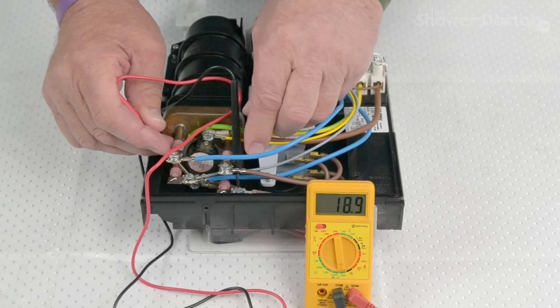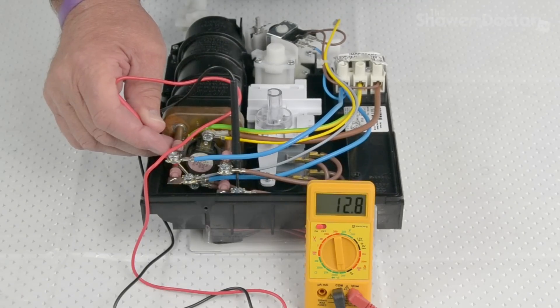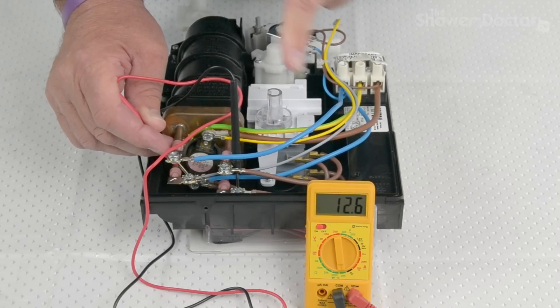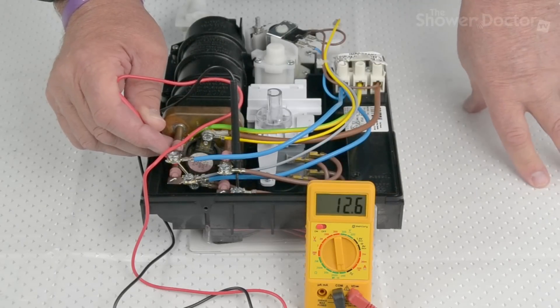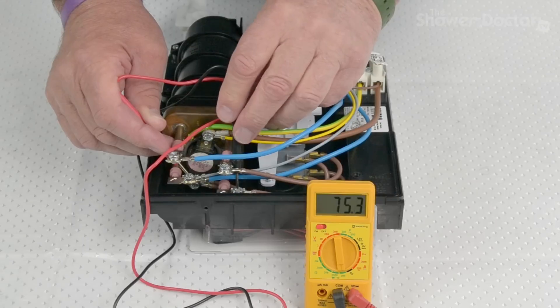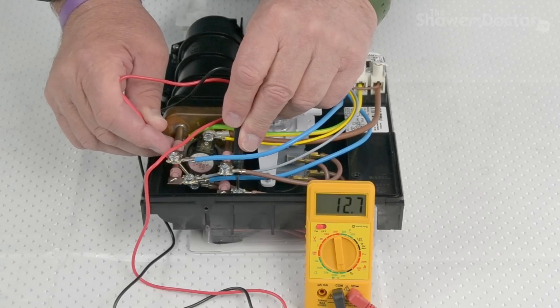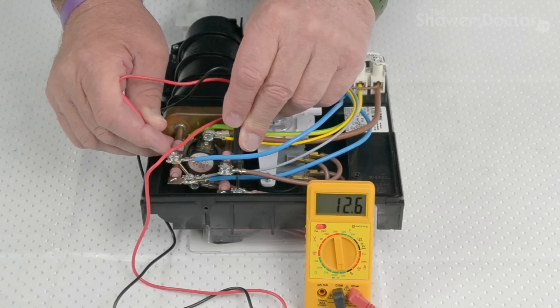If the element's faulty, there'll be really no reading at all. It'll read zero, or alternatively, you'll get some really weird readings. The meter will be jumping about all over the place. And so that's all you need to do to check the resistance in the ohms, in the elements.